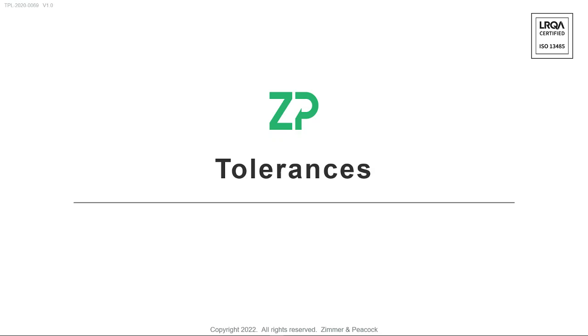So far, the general workflow is: people have a desire for a custom screen printed electrode, they might send a specification or drawings to ZP. Those documents will definitely talk about mechanical dimensions, they never talk about roughness, they sometimes talk about electrical resistance, but they never talk about actual electrochemical characterization of the screen printed electrode. For us, that means they're really just ignoring what's called the OQC, and we need to discuss that.